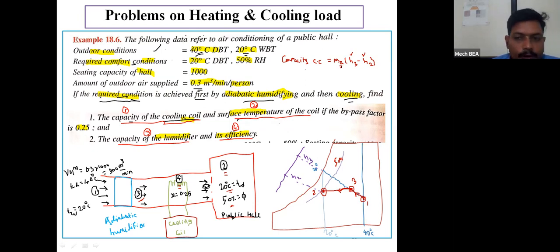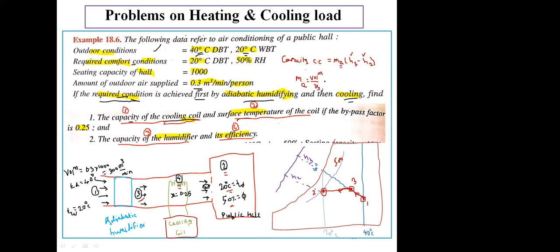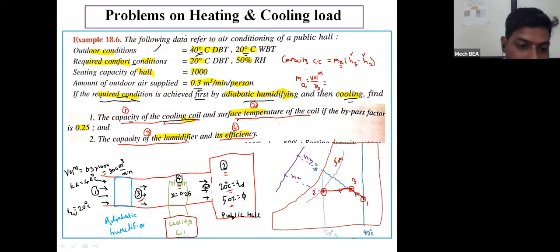So for calculation of mass of air, I am using the formula: mass of air equals volume divided by specific volume of entering air. I am knowing the value of volume of air supplied to the air conditioning apparatus, which is 300 meter cube per minute. And vs1, how to calculate that? vs1 means specific volume corresponding to point number 1.